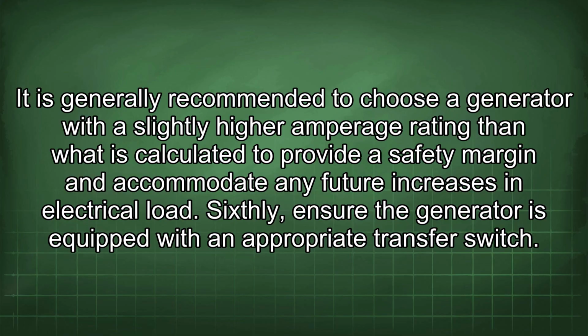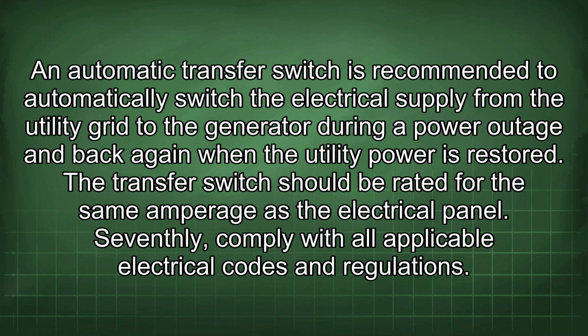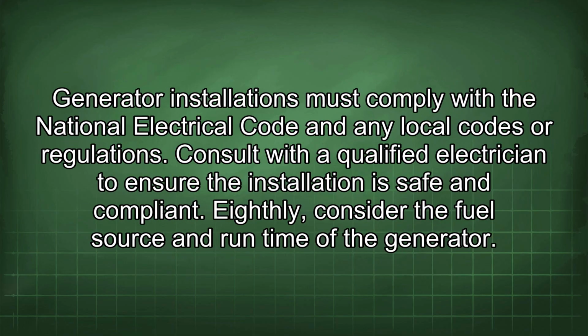Sixthly, ensure the generator is equipped with an appropriate transfer switch. An automatic transfer switch is recommended to automatically switch the electrical supply from the utility grid to the generator during a power outage and back again when the utility power is restored. The transfer switch should be rated for the same amperage as the electrical panel. Seventhly, comply with all applicable electrical codes and regulations. Generator installations must comply with the National Electrical Code and any local codes or regulations. Consult with a qualified electrician to ensure the installation is safe and compliant.